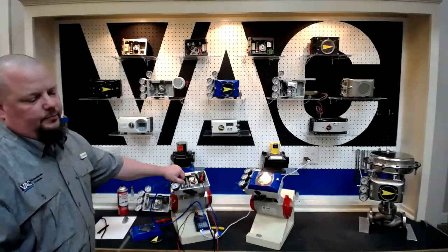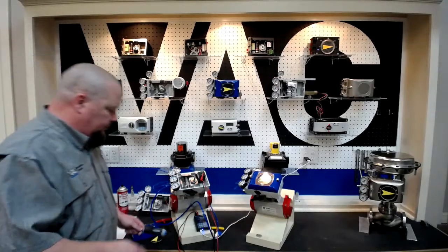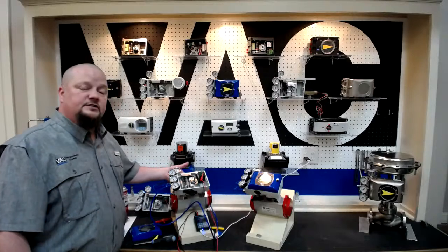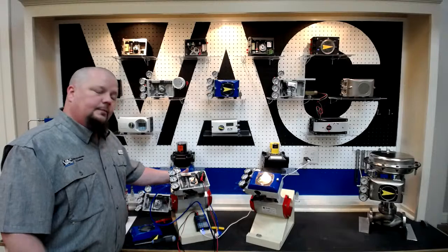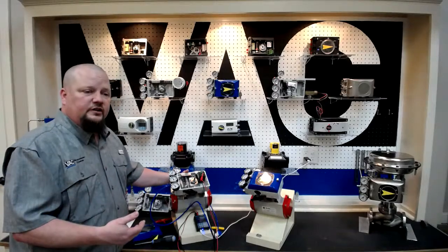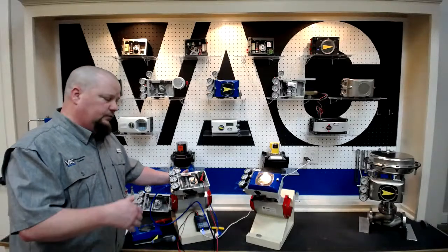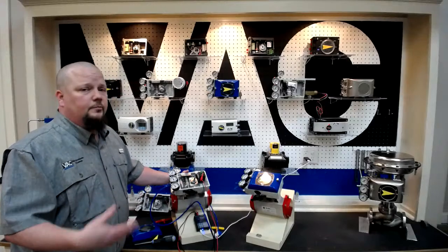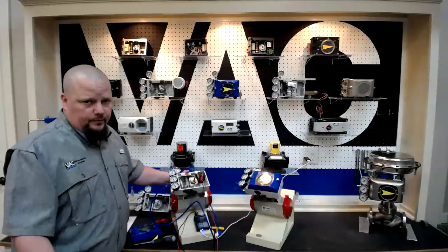Generally, when the cam is loose, there are a couple of different things that will show the same symptom: a loose cam or the spindle not engaged in the back of the positioner. What's going to happen is as soon as you start introducing a signal, it's going to drive fully open. Even if it doesn't take very much signal at all, it's going to drive fully open, and it's not going to modulate. So it defeats the whole purpose.